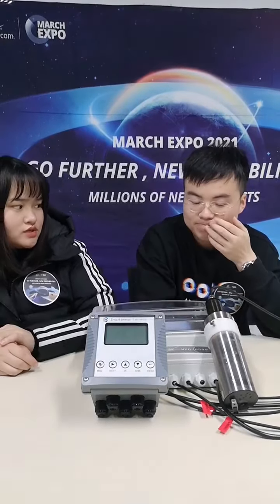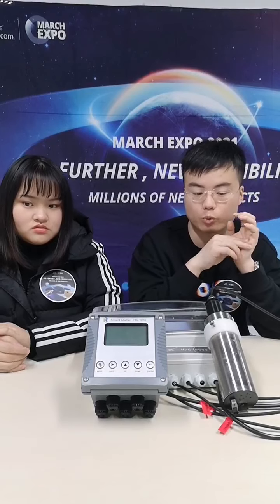But for drinking water, we cannot use this type, right? Because the range is out of the range. Yes, for this sensor the lower limit is 100 NTU. If it is below 100 NTU, we cannot get an accurate value from the sensor, so we won't suggest using this sensor in drinking water. But this controller is okay. So we can use another flow cell model, right? Yes, a flow cell with the optical principle, for low range turbidity.